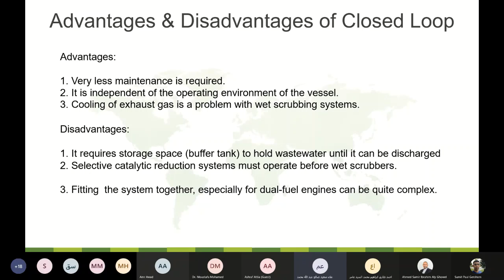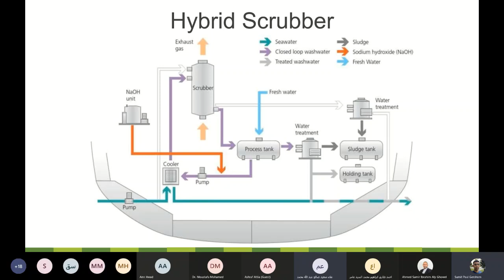This is the hybrid system, a combination of open loop and closed loop. If you see the blue line, you have the pump with suction from the sea going to the cooler, and there is a separate white line going to the scrubber — that white line indicates the open loop. It passes through the scrubber, then to water treatment, and directly overboard. That acts as the open loop. Then there is the same closed loop where water passes through the cooler and goes overboard, plus a separate freshwater loop. So this is just a combination of the two, giving owners the option of running on open loop or closed loop.